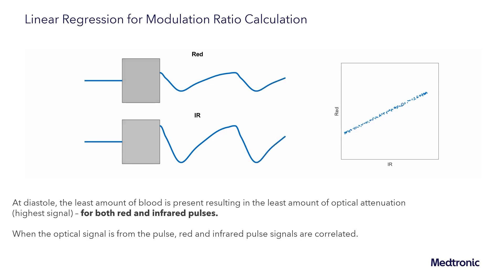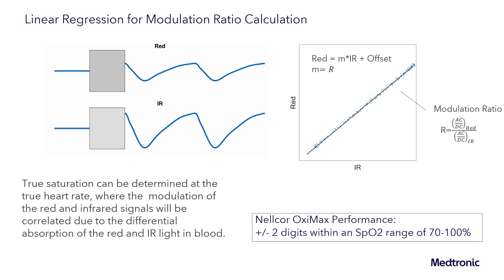If we think about why those signals would be correlated — why would the two signals change at different rates? They would change at different rates because they're being absorbed differently. As that blood volume changes during that pulse, the red and the infrared lights will change based on that relative absorption. And what we find is that if we perform a linear regression, the slope of that linear regression is going to provide us that modulation ratio. That modulation ratio can then be used to calculate SpO2. Moving through these steps is how Nellcor is able to achieve that plus or minus two digits of performance from a range of 70 to 100 percent saturation. Here, Nellcor finds the true saturation at the true heart rate of that patient.